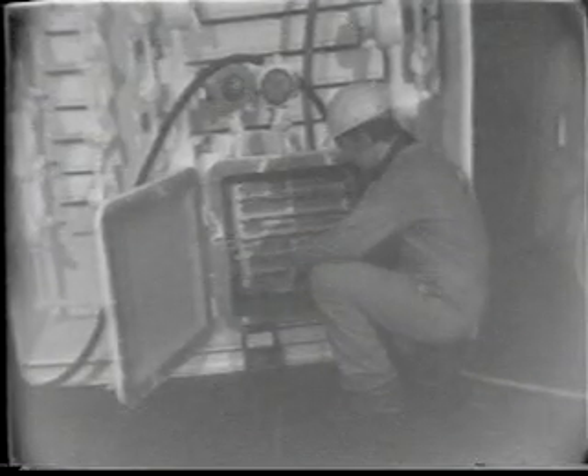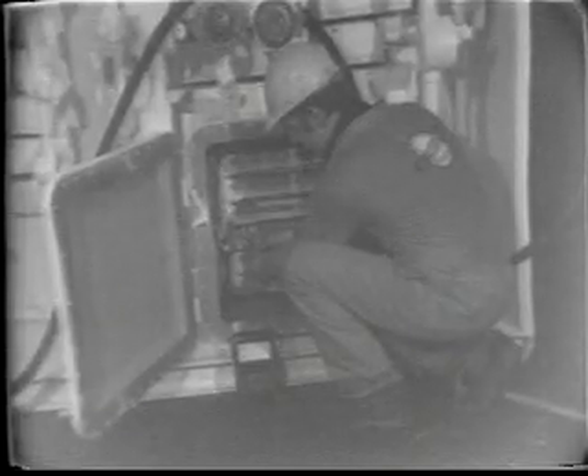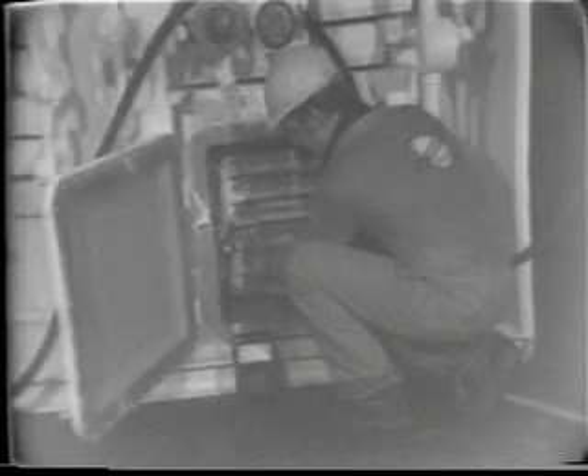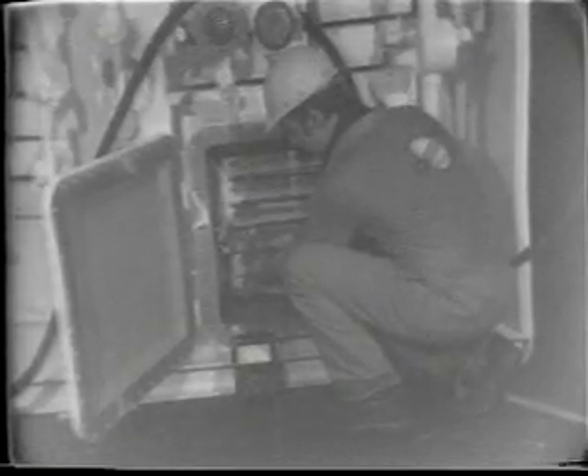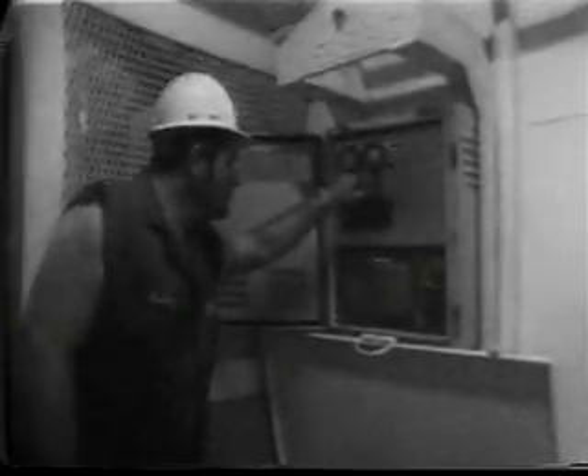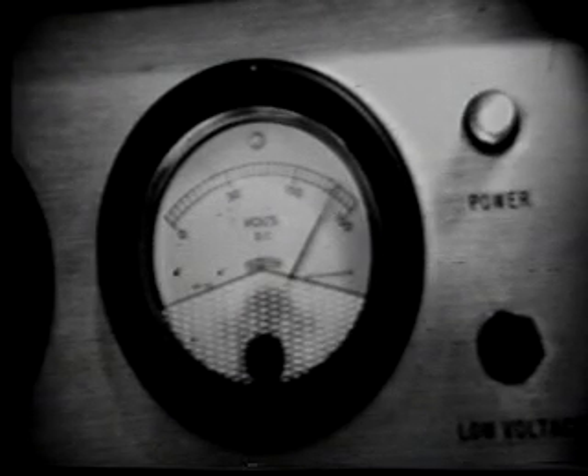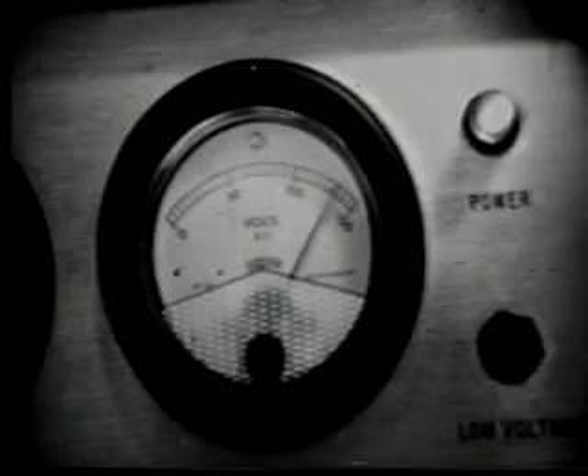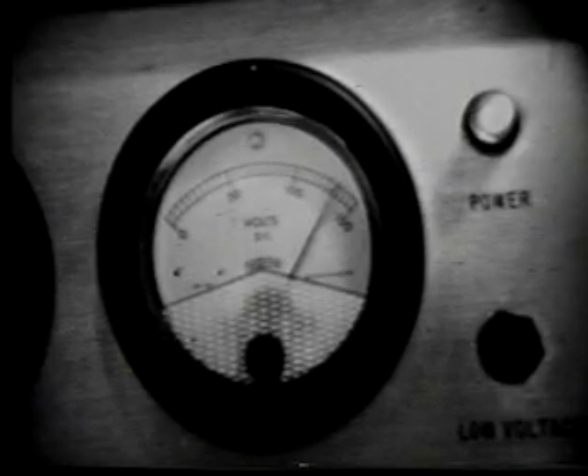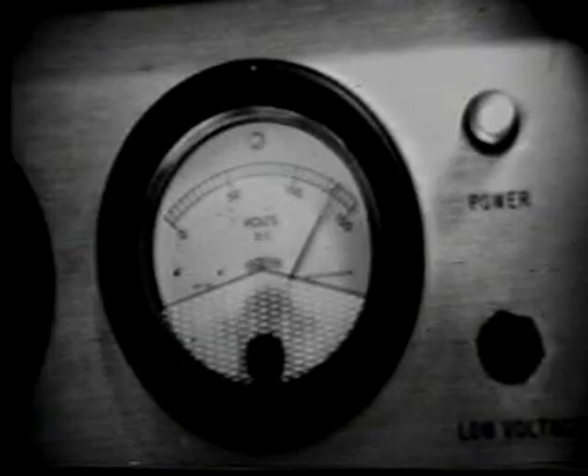If you want to be sure of the voltage, check the schematic, locate the input voltage wires, and then use your voltmeter to make sure you have the proper voltage as indicated on the schematic. If the lights on the panel are dim, then there are several items for you to check. First, check the output meter of the battery charger. This should be 120 volts DC or 24 volts DC as required. If you are not getting adequate voltage, then have the rig electrician check the rig's power supply to the system.